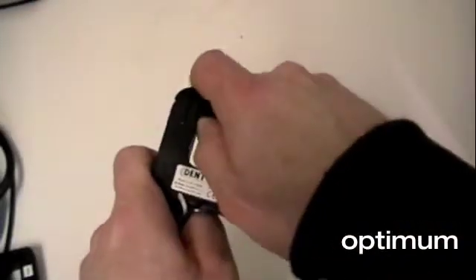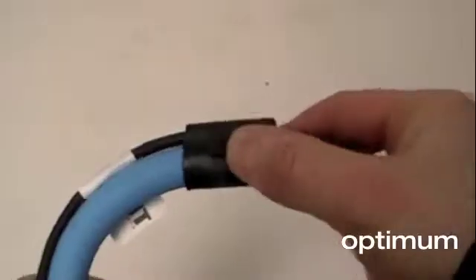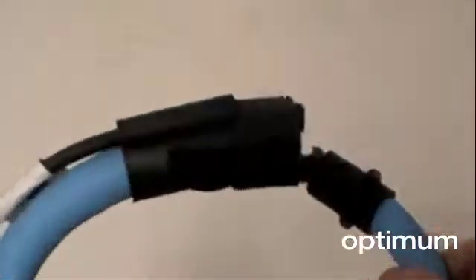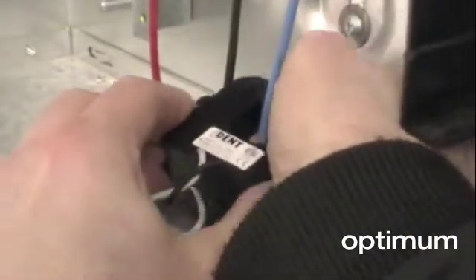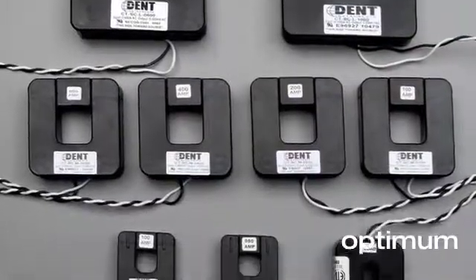PowerScouts work with either split core and roll coil flexible current transformers. Both types have a millivolt output so they are much safer to work with than a conventional 5 amp CT. Split core current transformers are available from 50 amps to 1000 amps. There is a high accuracy version for measuring 0-5 amp secondary and compact 50 amp CTs for measuring branch circuits.